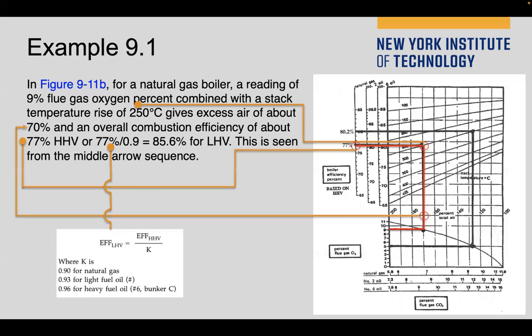So first of all, this example appears in your textbook, figure 9.11b: a natural gas boiler reading 9% flue gas oxygen percentage, combined with a stack temperature rise of 250 degrees Celsius, gives excess air of about 70% and an overall combustion efficiency of about 77%.